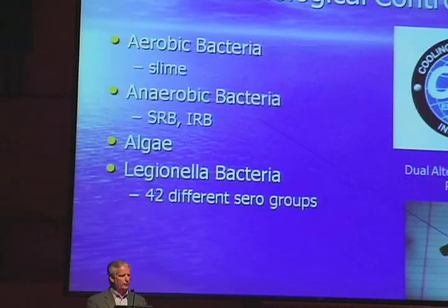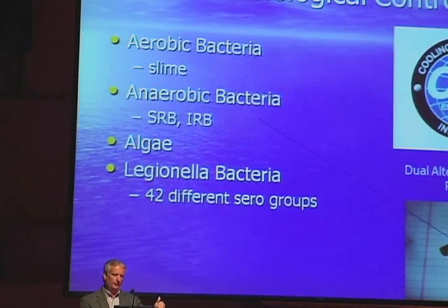And then, of course, we got algae. Now, we don't see algae in condensers because there's no sunlight. The only place we see algae is where there's sunlight. So if you can find a way to enclose your cooling tower where there's no sunlight, life is good. You won't see algae. And then, of course, there's Legionella. We'll talk a little about that in a later segment. What we normally find around the country is that if you control your aerobic bacteria to within normal performance standards, we normally don't see issues with Legionella. Now, that might vary a little bit with healthcare. We'll talk a little bit about that later.